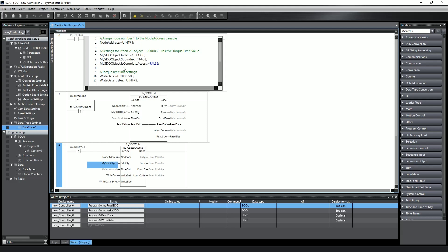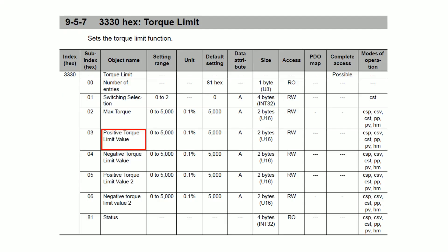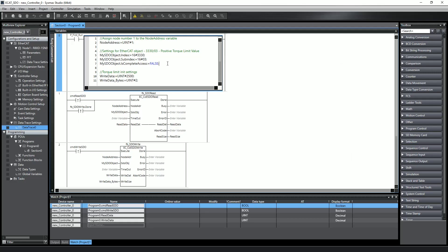For this example, I'm going to read and write values to the positive torque limit setting in the drive. The table in the 1S manual shows the EtherCAT object for torque limit settings is 3330, and the sub-index for the positive torque limit setting is 3. So in my structured text block, I set the data structure elements of the mySDO_object variable using the object address information from the manual. I set the index value to 3330, and these are hex values, so I have the 16-pound qualifier before the value to indicate that it's hex. I set the sub-index to 3, and since I'm only going to work with the positive torque limit setting, I set is_complete_access to false.